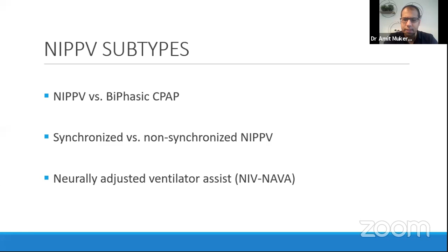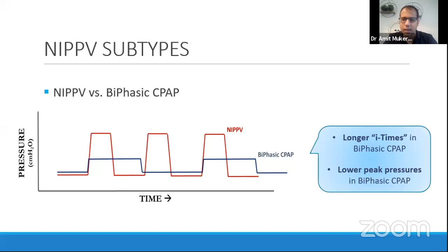So to touch briefly on NIPPV and biphasic CPAP, this image actually illustrates the difference between them well. NIPPV is really intended to mimic tidal ventilation. So it has relatively shorter I times and higher peak pressures, whereas biphasic CPAP conceptually could be understood as simply 2 levels of CPAP, and the baby is allowed to breathe spontaneously around what is essentially 2 different levels of CPAP. So the quote-unquote I times are longer, and the peak pressures are generally lower than what we give during traditional NIPPV. But sometimes there's a bit of a gray zone between these two modes, and you may have a combination of settings which is in between biphasic CPAP and NIPPV.